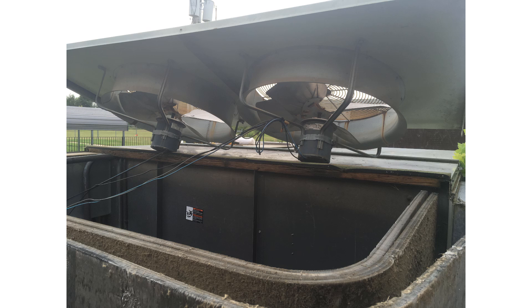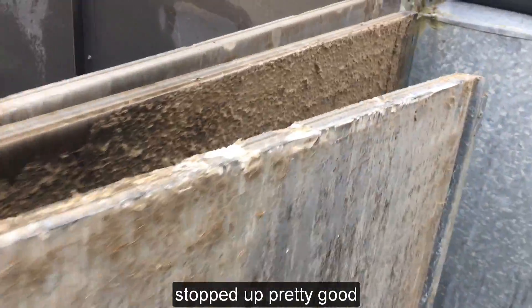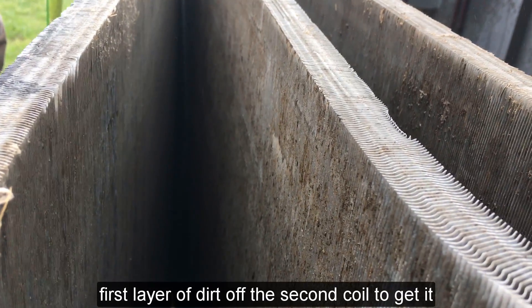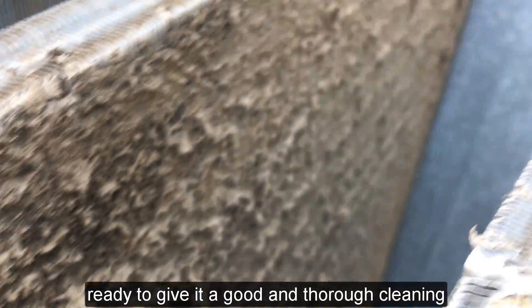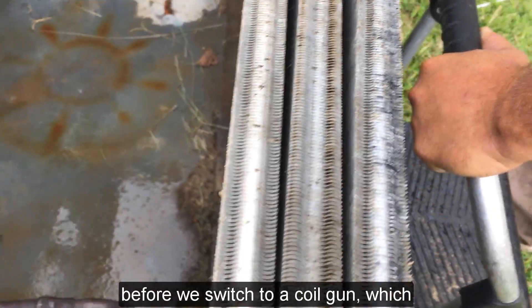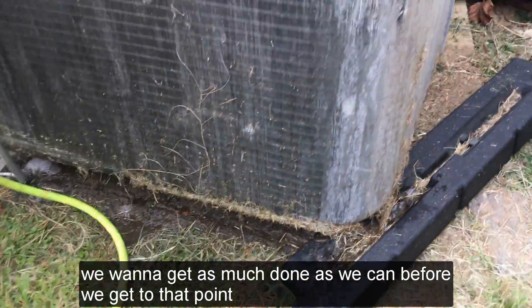Here we go — this is Jeff Casey. We've got the Voyager 20-ton package unit condenser coil stopped up pretty good. What we're doing now is just knocking the first layer of dirt off of the second coil to get it ready to give it a good and thorough cleaning. We'll get as much of this stuff knocked off as we can before we switch to a coil gun — a little better reach but not quite as much pressure.